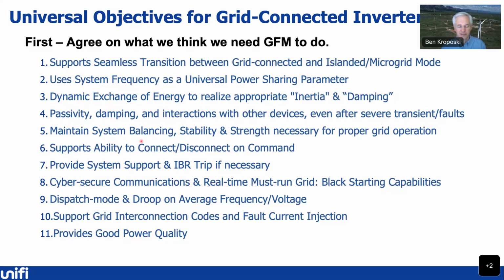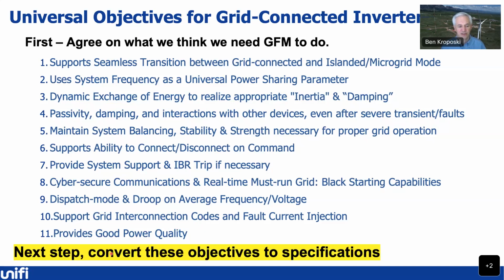that they maintain system balancing and stability, support the ability to be connected or disconnected, support the ability to trip if necessary, use cyber-secure communications, including black start, be able to be dispatched and use droop, which is how the system operates today, and then look at how to support interconnection grids and fault current injection and provide good power quality. Those are the universal things that we thought we should be able to accomplish with these specifications.